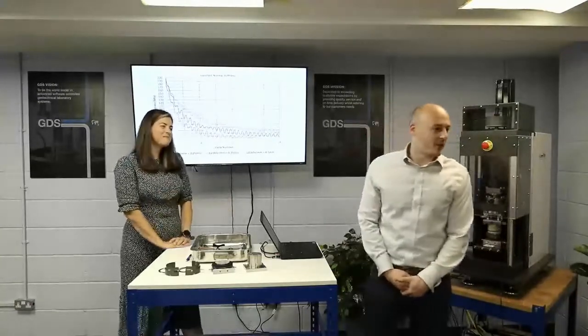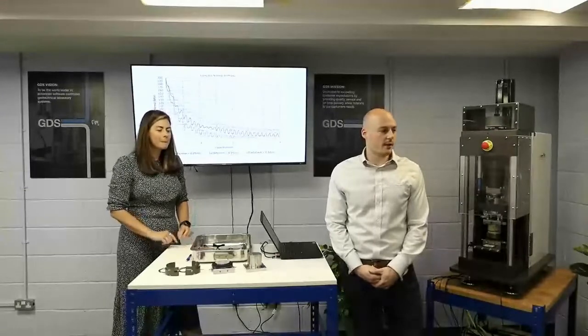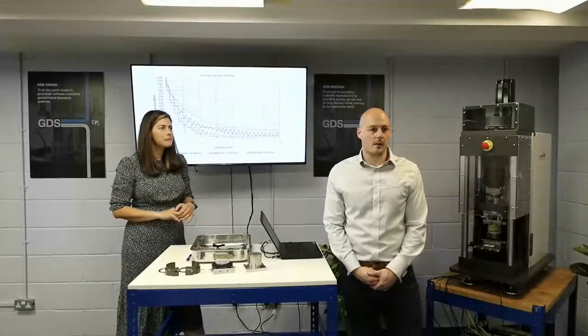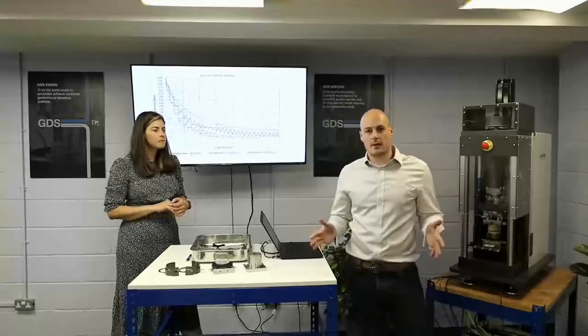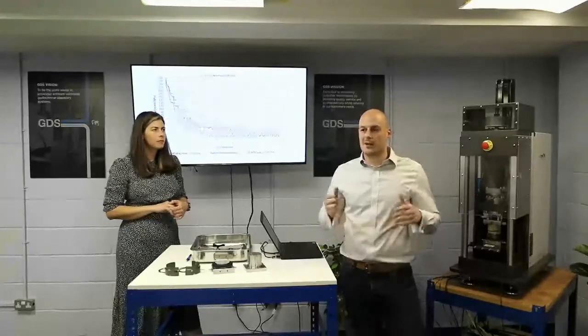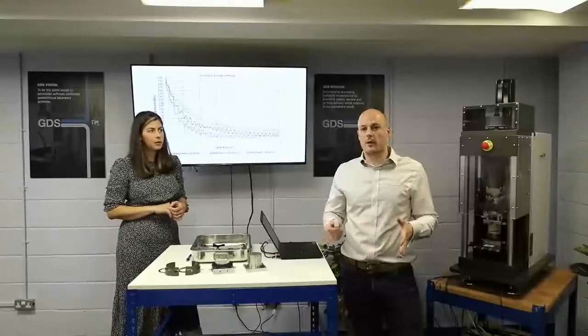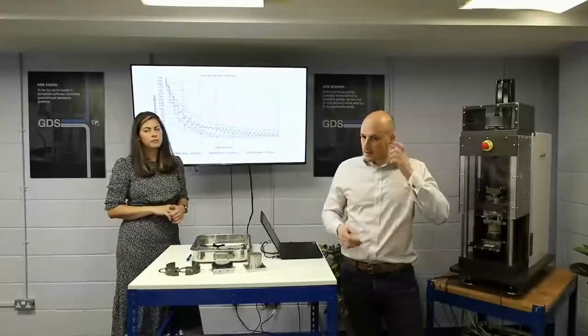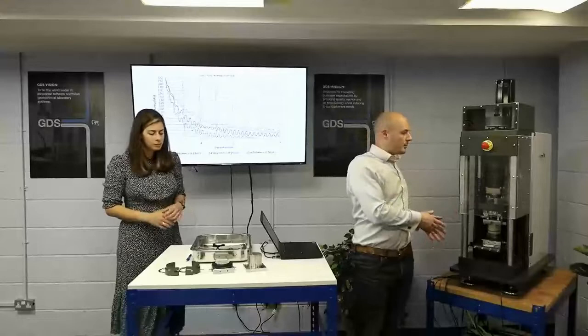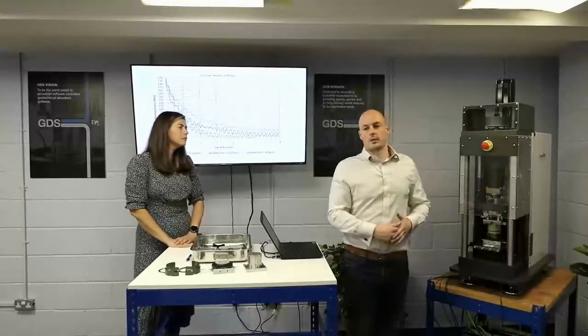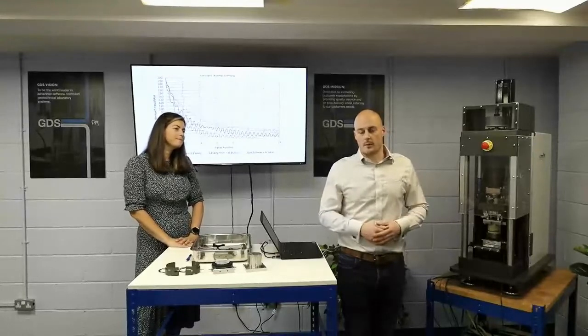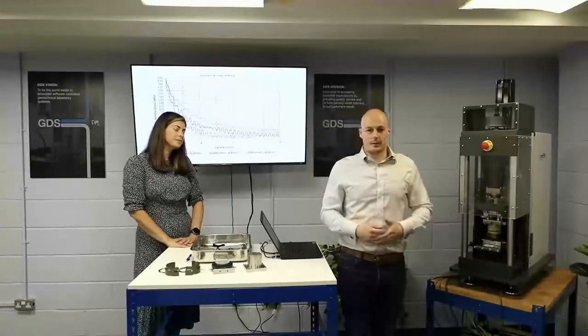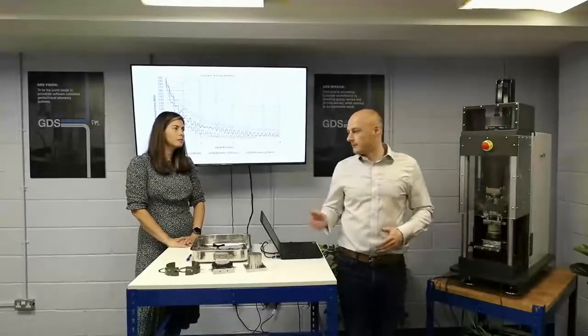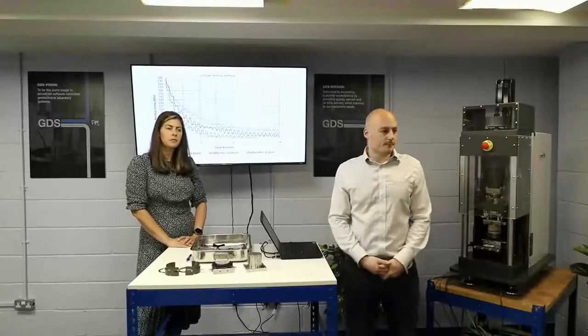Sorry. For the first one that came through, about irregular periods and custom waveforms: the custom waveform, we can load in 1,000 points. So irregular waveforms, yes, you can load in an earthquake waveform, for example, with multiple peaks. Obviously, the amplitude and the frequency you set in the machine will be determined by how rapidly you want that to change within that period of time. So yes, it can be done, but there are some limitations around making sure you get the right amplitudes and frequencies set in there to run that irregular waveform within those 1,000 points.